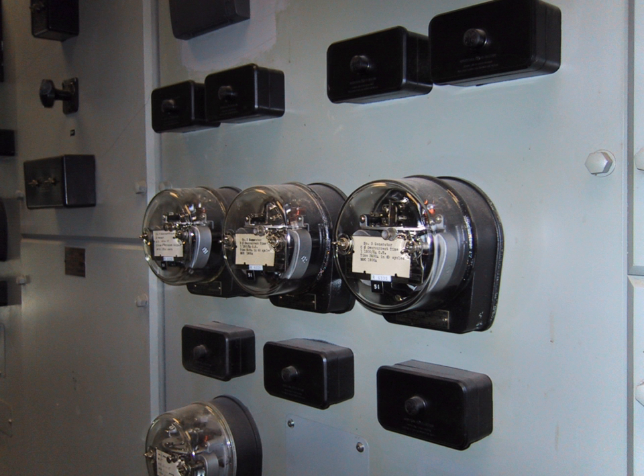Topic: Power source. The relays can also be classified on the type of power source that they use to work. Self-powered relays operate on energy derived from the protected circuit, through the current transformers used to measure line current, for example. This eliminates the cost and reliability question of a separate supply. Auxiliary-powered relays rely on a battery or external AC supply. Some relays can use either AC or DC. The auxiliary supply must be highly reliable during a system fault.